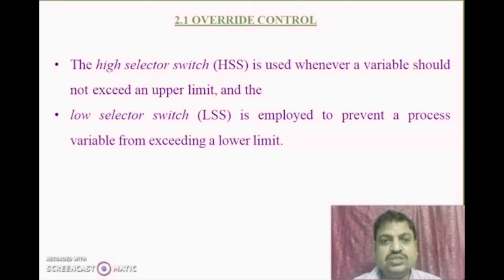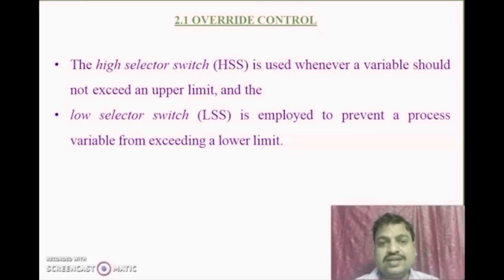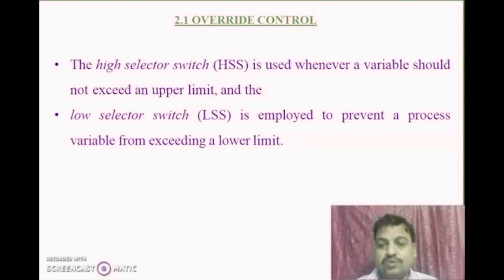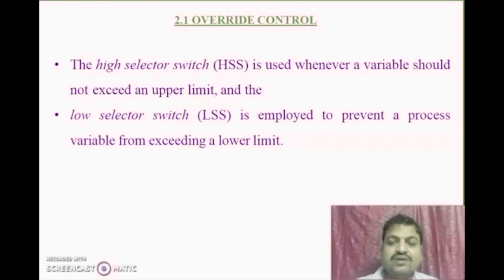HSS is also called the High Selector Switch. It is used whenever a variable should not exceed an upper limit. Similarly, Low Selector Switch is used whenever a variable should not fall below the lower limit. Whenever the value falls below the lower limit, the LSS will activate. Similarly, whenever the value exceeds the upper limit, HSS will activate.